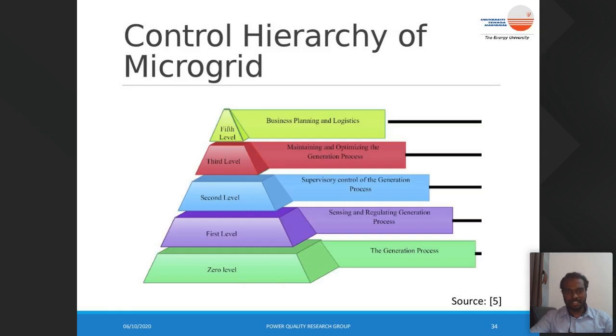To mention here, the 0th level control pertains to controlling the distributed generation, and the 1st level control pertains to maintaining the frequency and voltage. The 2nd level control is the one which sets the reference frequency and voltage reference for the below 2 levels of control. And the 3rd level control, which is the tertiary control, maintains the optimal operation of the microgrid and allows different configurations with respect to the grid.